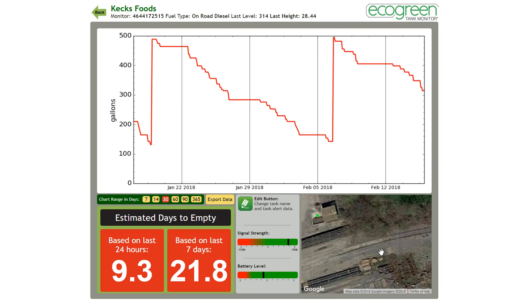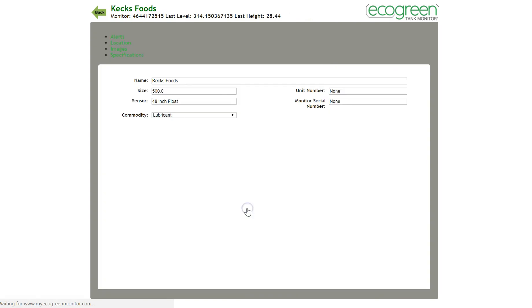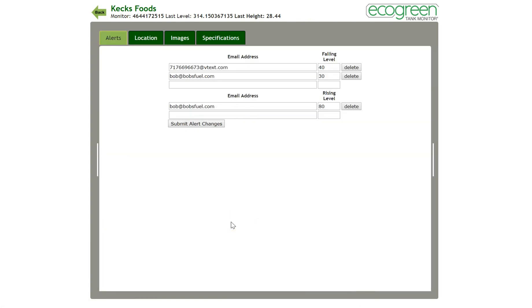The middle of the screen has an edit button, which drills down to more information and options. The first tab is where you set up email and text alerts. The falling level alert lets you know when the tank falls to a certain level — in this case, 40% and 30%. You also get rising level alerts; in this example, it's set at 80%. You can create as many alerts as you need, and they go as either emails or text messages.